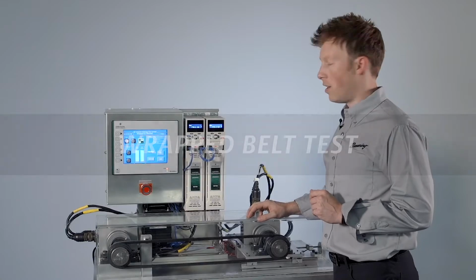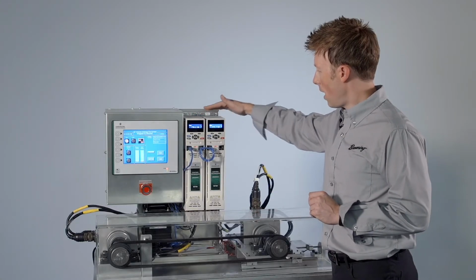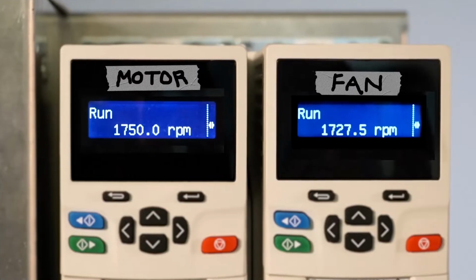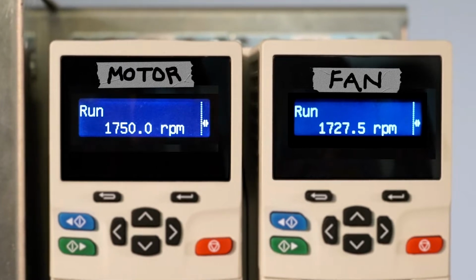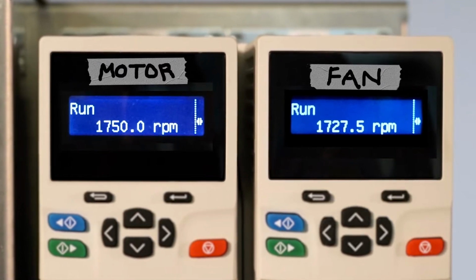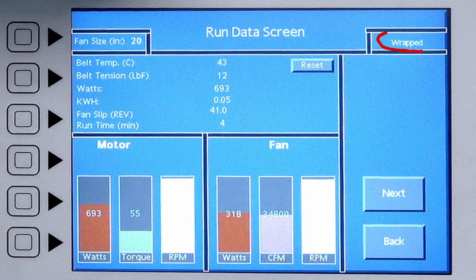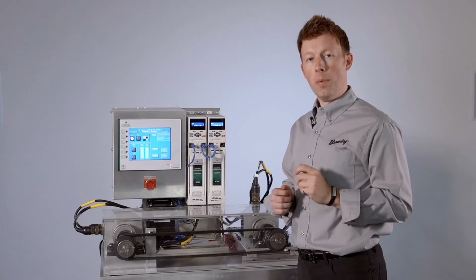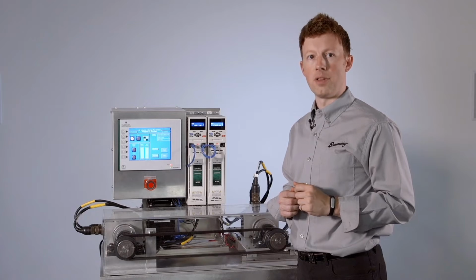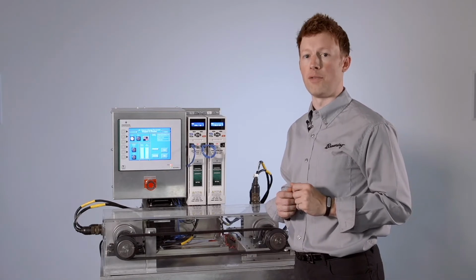So what you can see here is the speed of the motor and the speed of the fan. The fan has a much lower RPM because the belt is slipping on the driven sheave. You can also see the kilowatt consumption of the motor. It's sitting at around 650 to 750 watts. We'll be running a 10-minute test and capturing the total energy used and the total airflow generated.